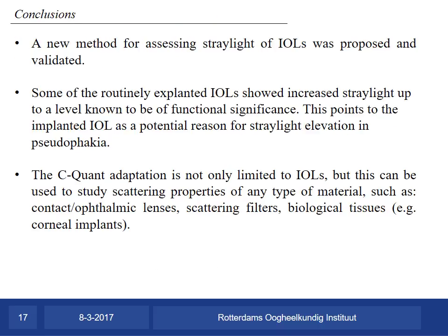In conclusion, a new method for assessing straylight of intraocular lenses was proposed and validated. Some of the routinely explanted intraocular lenses showed increased straylight up to a level known to be of functional significance, and this points to the IOL as a potential reason for straylight elevation in pseudophakia.